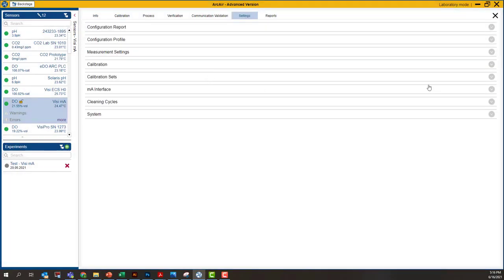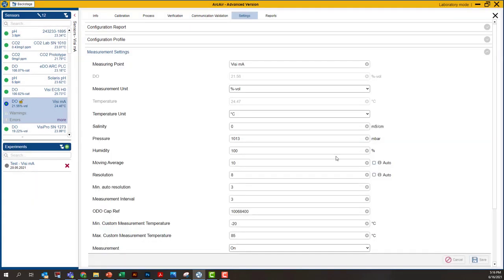So let's go through and look at the settings in the sensor. I'm going to go to measurement settings here. There we go. At this point in the sensor, I have a value for atmospheric pressure, and it just so happens that we used sea level here. What happens if I change this? Well, I'm going to cut this in half, roughly in half. I'll cut it to 500 millibar. And let's see what happens.